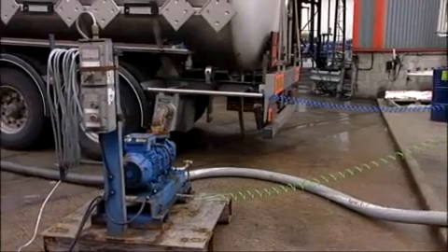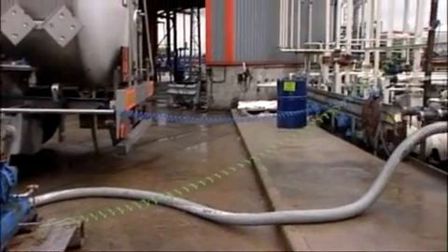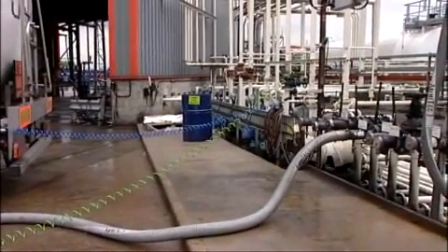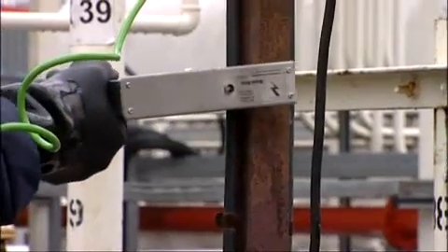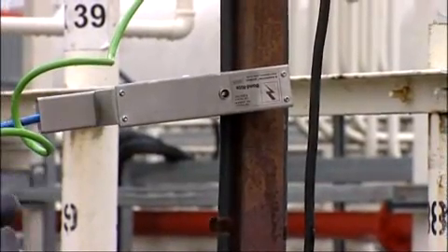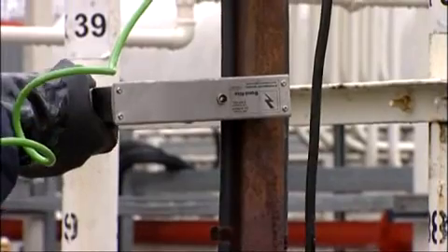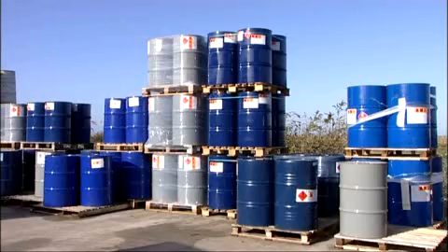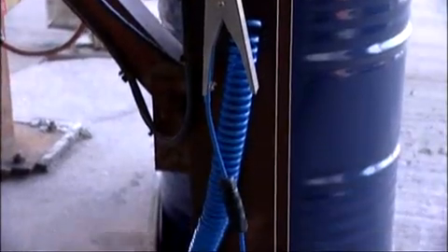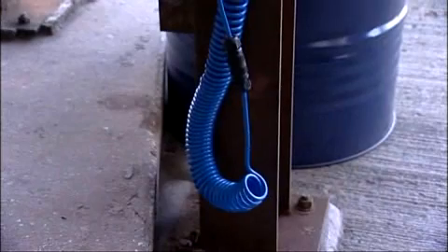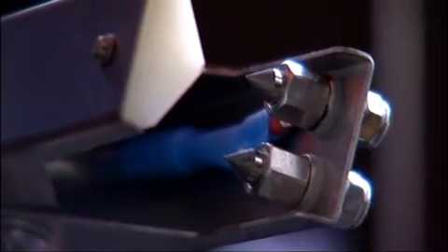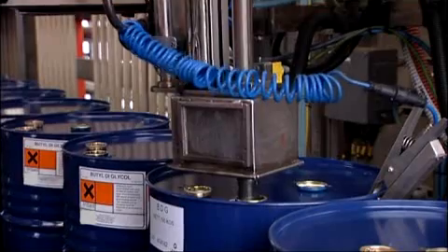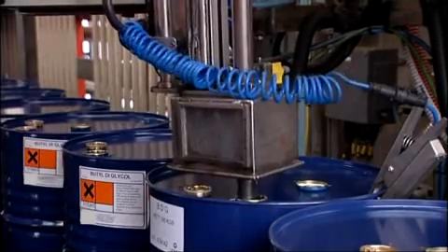Portable equipment must be earthed back to the process equipment or common earthing system, using the appropriate flexible cables and clamp. The clamp must make contact with metal surfaces through paint, rust, and surface contaminants. Drums and cans must be earthed back to the loading system via earth leads and a special earthing clamp that penetrates the paint coating. Preferably, the earthing clamp is in a separate location to the source of the flammable atmosphere.